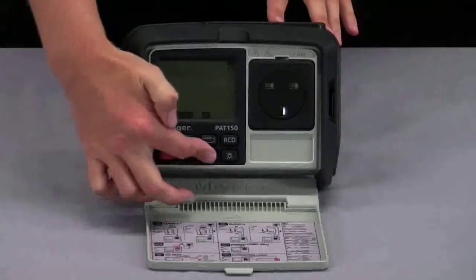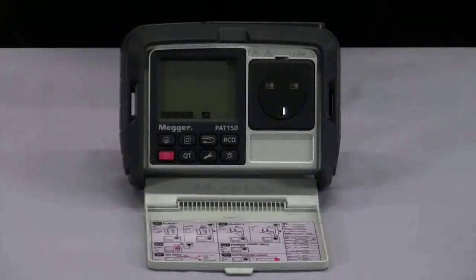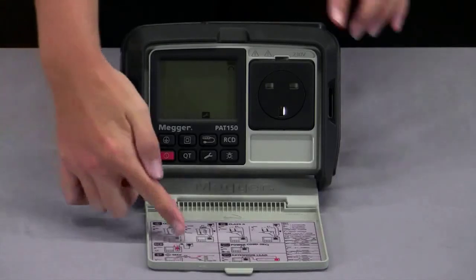The setup mode allows me to null out the resistance of my earth continuity and IEC leads, as well as change any values in the automated test modes. For example, if you have an appliance that has a long lead, you may need to adjust the continuity value to compensate for this. The default original values can be seen on the Quick Start guide in the lid.